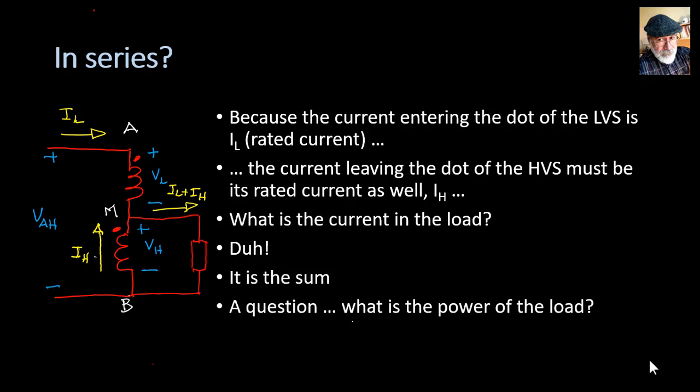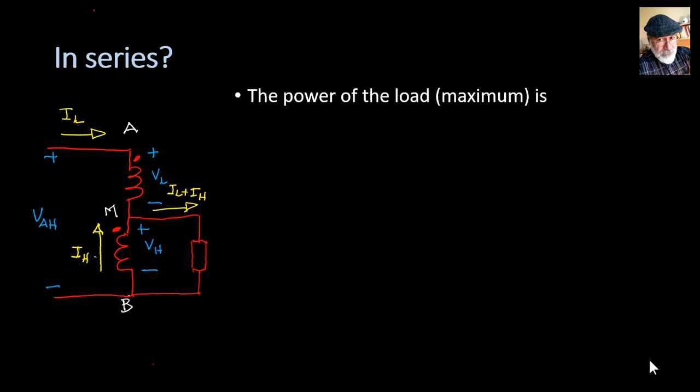I have a question for you. What is the power of the load? Multiply them. Of course, the power of the load is the maximum power that we can feed with this arrangement. Why? Because I already have both windings at the rated current, so I cannot exceed that. So the maximum power of the load is VH, the rated voltage of the high side, multiplied by the sum of the rated currents of the low side and the high side.